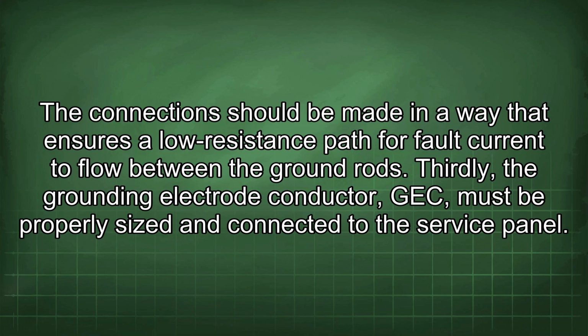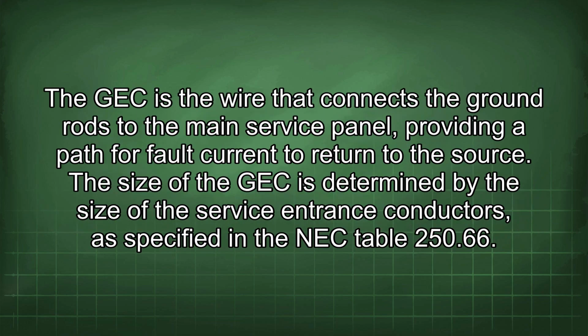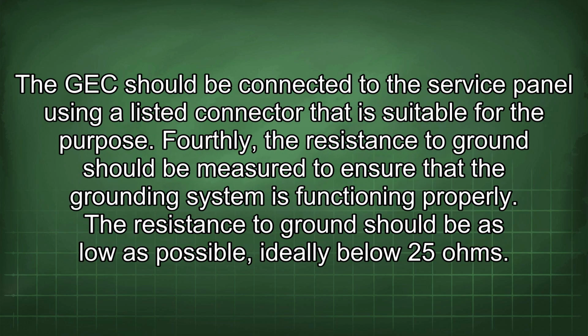Thirdly, the grounding electrode conductor, GEC, must be properly sized and connected to the service panel. The GEC is the wire that connects the ground rods to the main service panel, providing a path for fault current to return to the source. The size of the GEC is determined by the size of the service entrance conductors, as specified in the NEC Table 250.66. The GEC should be connected to the service panel using a listed connector that is suitable for the purpose.